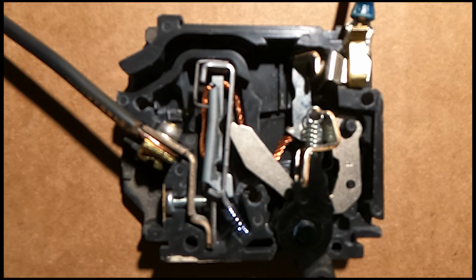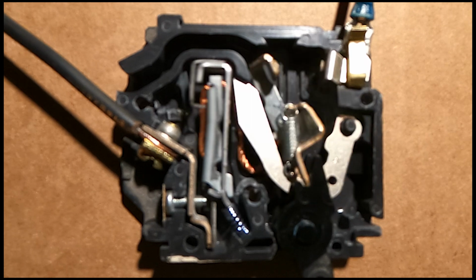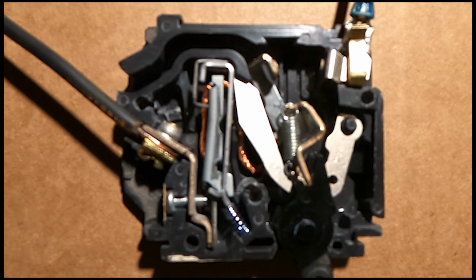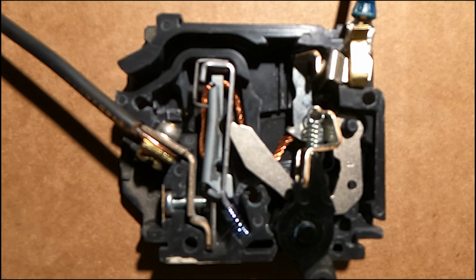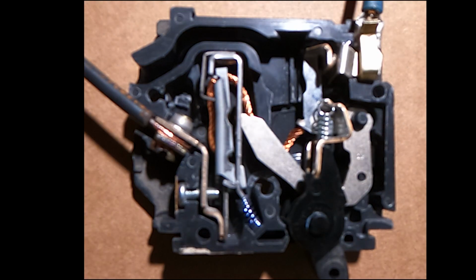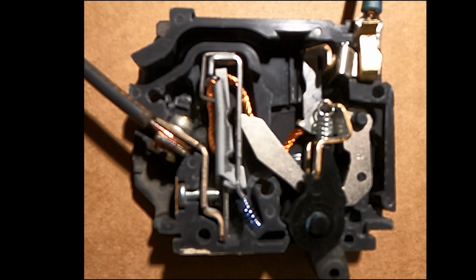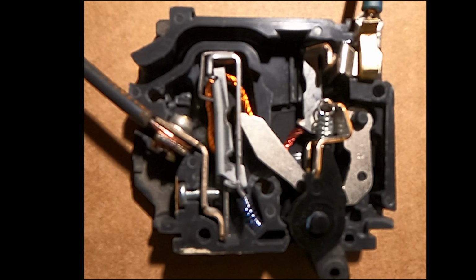And here it is one more time. So this is where we try to overload the circuit. And this is the bimetallic strip, which runs almost all the way to the end of the armature. Watch for this strip to bend away to the left of the screen, unlatching it so it can disconnect the circuit. While you're watching this, most residential breakers that I'm aware of come with what's called a time current curve or a trip curve, which is a graph explaining when the breaker will trip and under what circumstances. And I'll go over that next.